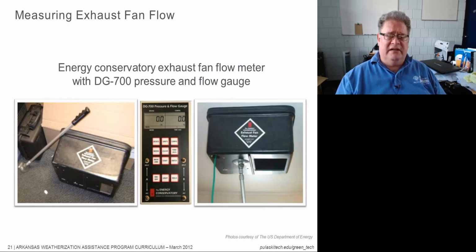So you connect it up, and we'll have a demo video of how to use one of these. There's just a few little things that you have to remember when you use this. But once you do, it's pretty easy to use. It's basically just a calibrated pressure pan with a hole in it, and you don't need to use it with a DG700. You can use it with just about any good manometer, but the DG700 does have the exhaust fan flow hood or exhaust fan flow meter built in as a device.